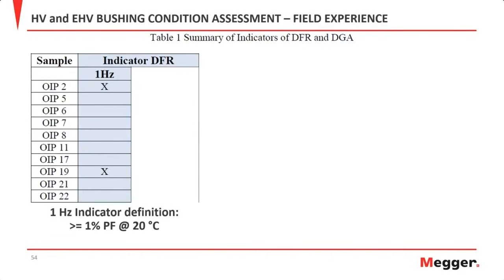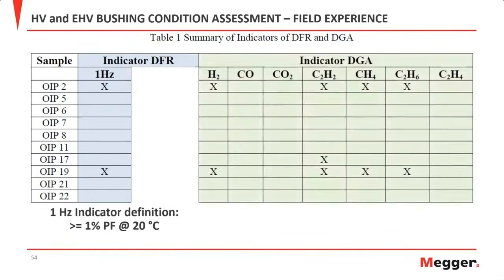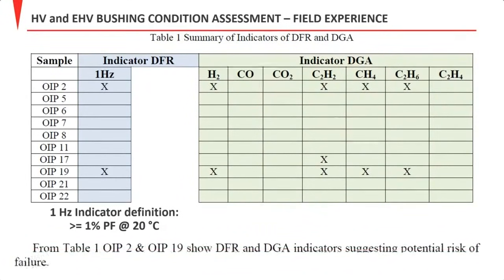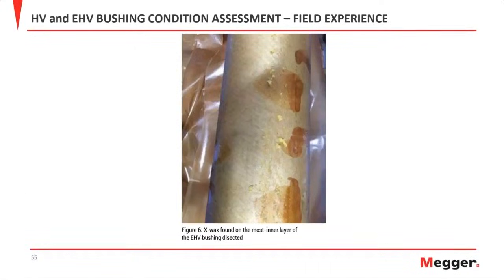Then when we look at the DGA examples, we see that where there were high 1 hertz values and high DGA levels for hydrogen, acetylene, methane, and ethane, they correlated very nicely to one another. And since these two bushings showed some potential risk of failure, they were then deconstructed, and what they found inside was that one of the byproducts of having this oil and paper inside is you get this X-wax, and it was found on the innermost layer of these extra high voltage bushings. So this corresponded directly to the DGA and the 1 hertz measurements that were made before.